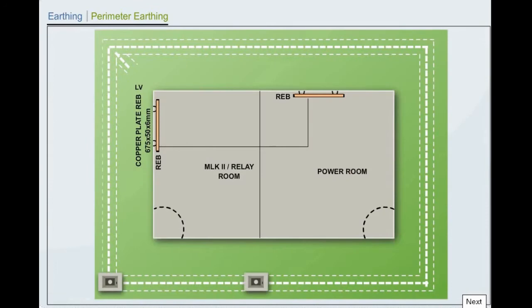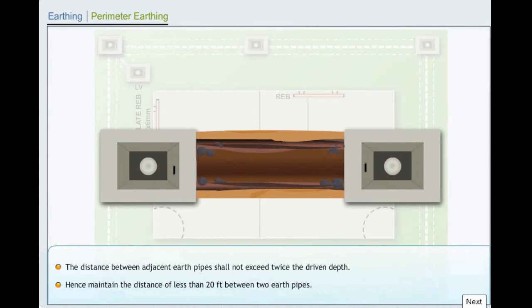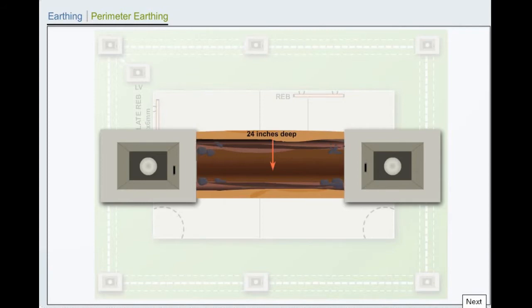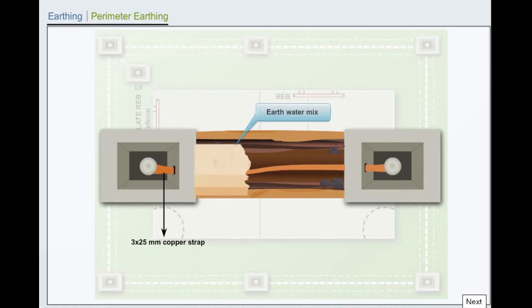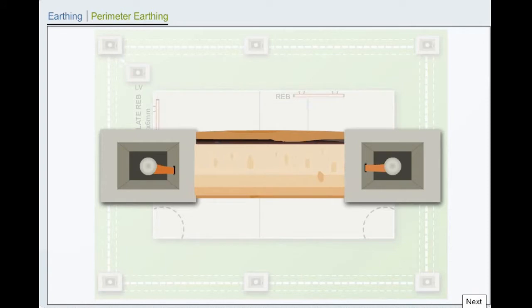Earthing. Perimeter earthing. In perimeter earthing, earthing electrodes are required to be provided surrounding the equipment room and power room. The distance between adjacent earth pipes shall not exceed twice the driven depth. Hence, maintain a distance of less than 20 feet between 2 earth pipes. A trench of 24 inches deep and 12 inches wide is to be dug between all earth pipes to accommodate 3 by 25 mm copper strap for interconnection of successive earth pipes. The entire trench is to be covered with earth-water mix.